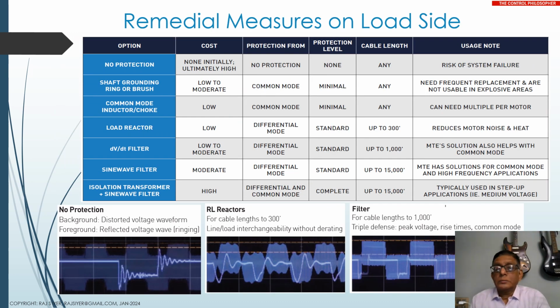Okay, this table shows what can be done on the load side. Typically, to prevent the harmonic induced eddy currents passing through the body of the motor, you can use a shaft grounding ring or brush. You know, then there's an amount of wear and tear involved with it. So in this case, it is better to use a motor that has the ball bearing set in a way that is insulated from the motor body.